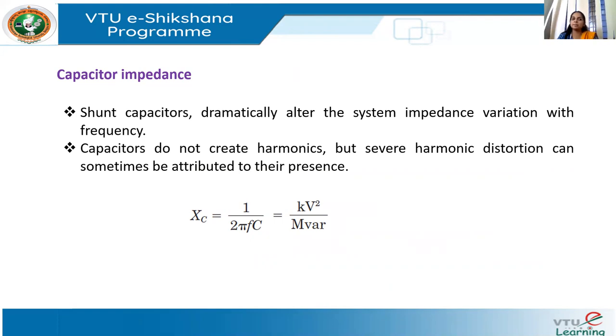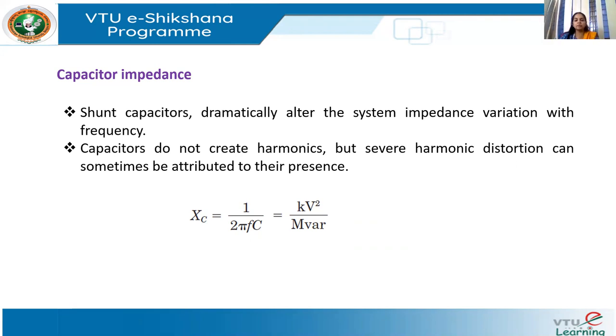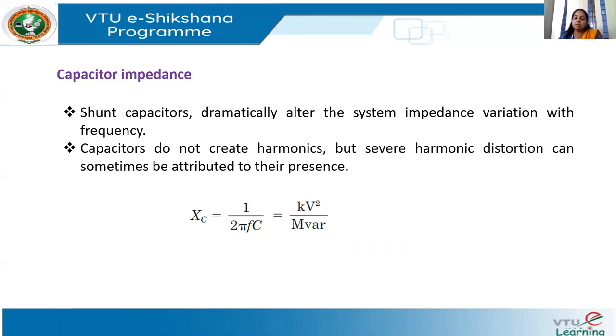This severe harmonic distortion mainly occurs when the capacitance acts with other system parameters to cause either series resonance or parallel resonance. The capacitor impedance can also be calculated as kV² divided by MVAR if the MVAR rating is known. The main system parameters which can affect or be affected by harmonics in the system have now been covered.